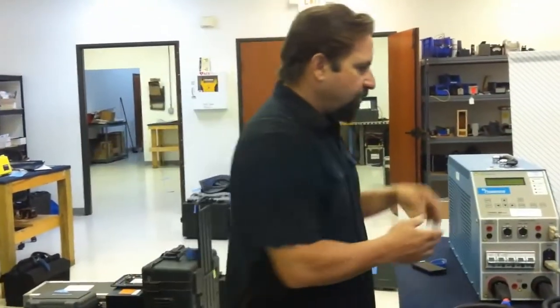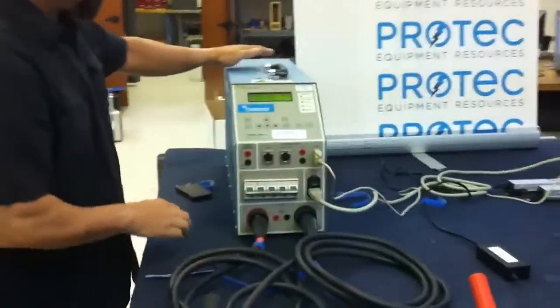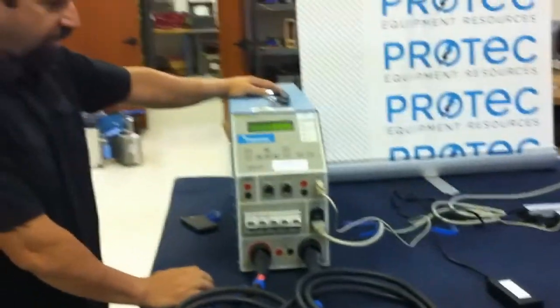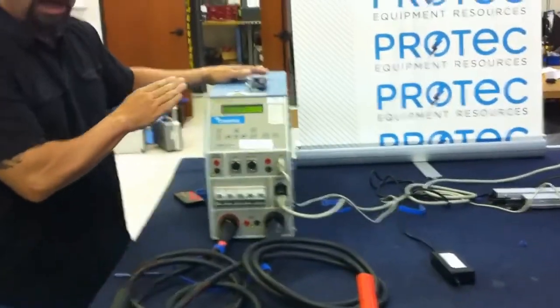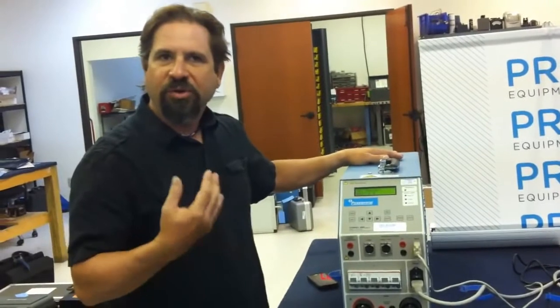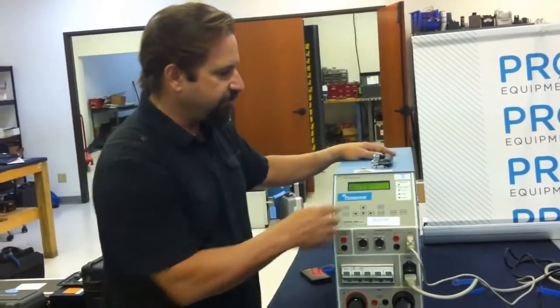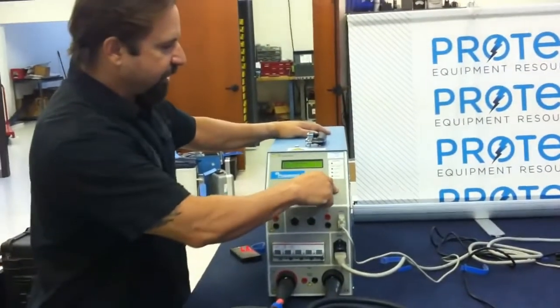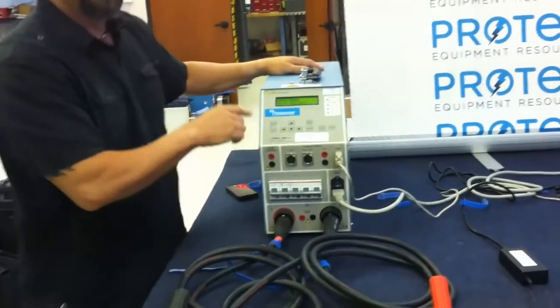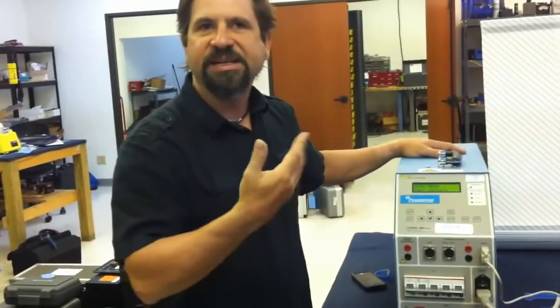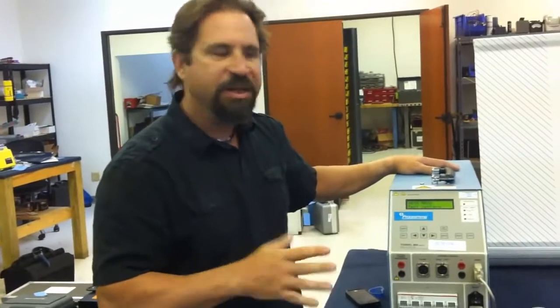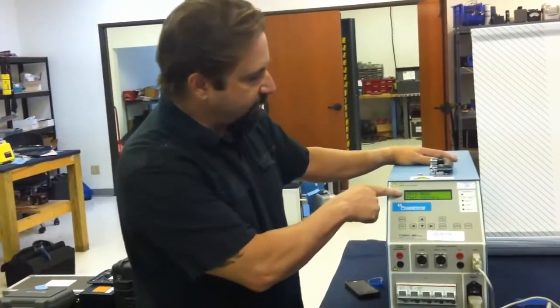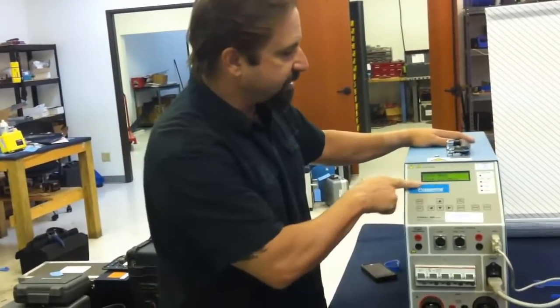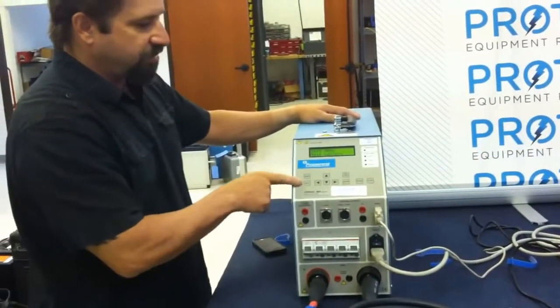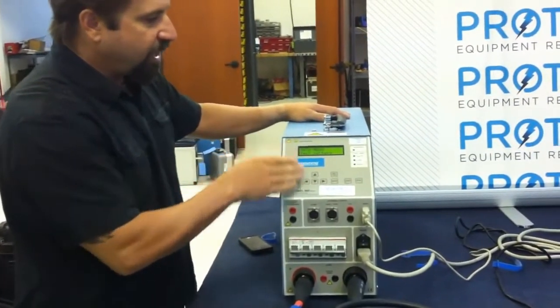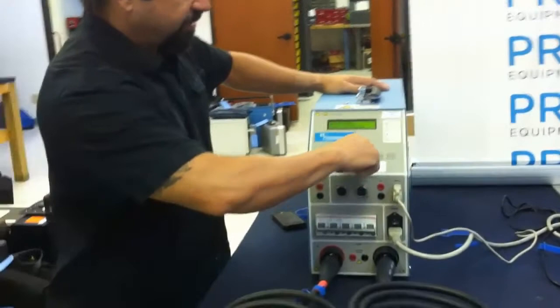Okay, now we're ready to turn the TORKEL on. I'd highly recommend that if you're renting the TORKEL, the very first thing you do when you receive it is hit your stop key and escape key, just in case a previous test was running and got interrupted. This clears out anything in the TORKEL and brings you back to the main menu where it says Test Battery. Hit escape to get back to that point, then select Test Battery and hit OK or enter.